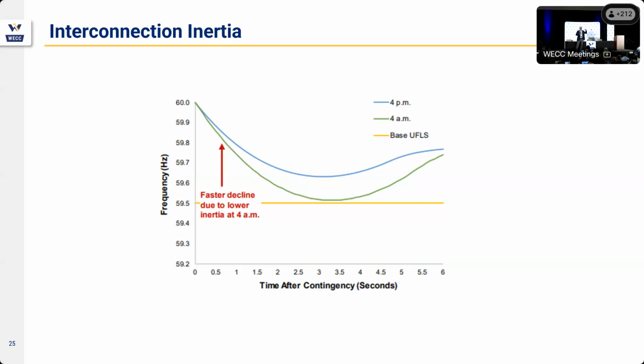So one of the aspects of BAL3 is we're measuring the performance at the BA level. But if we recover frequency back to 60 during the measurement period, there's nothing to measure. That's a good thing. It used to take 4 to 5 minutes to recover frequency back to nominal. We're doing it in 20 to 52 seconds a lot of the time in the West. And usually it's when batteries are active. So Glenn, they do provide a very, very good and solid response.